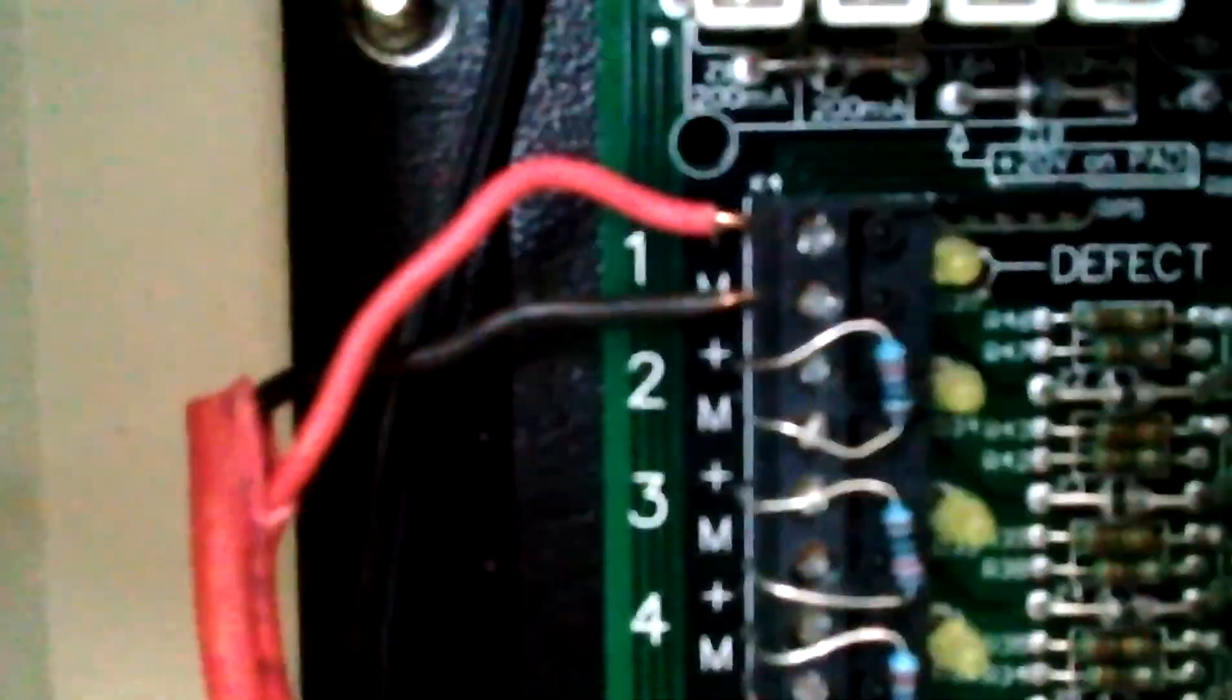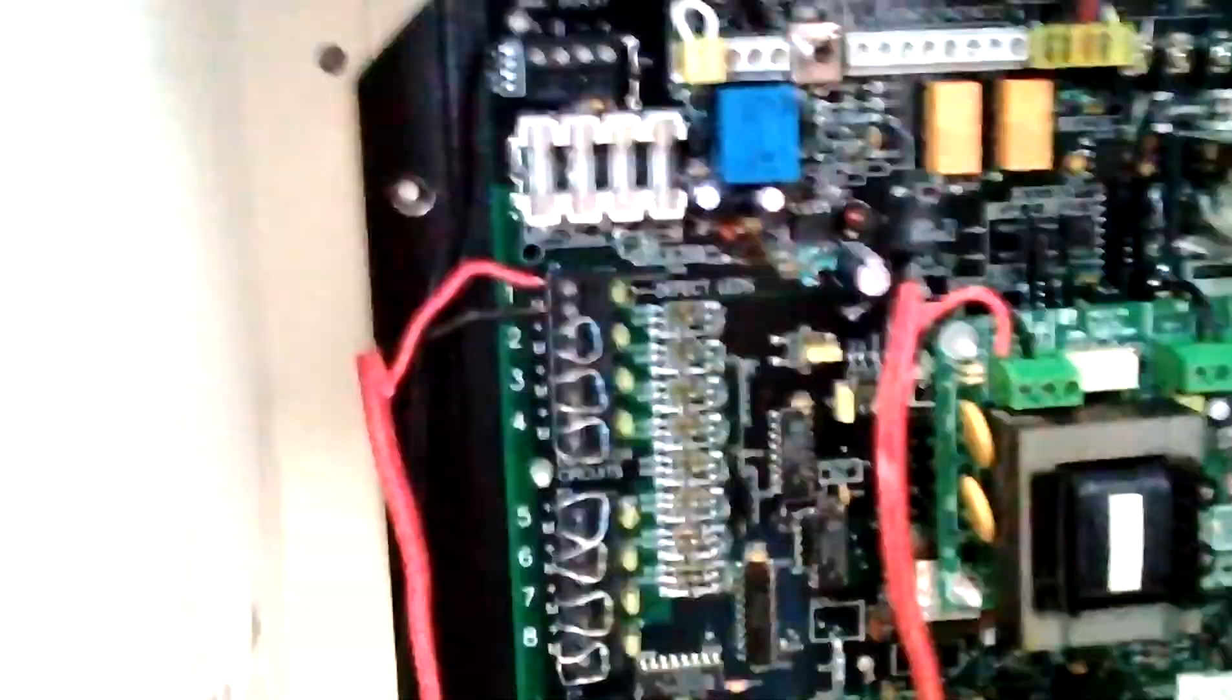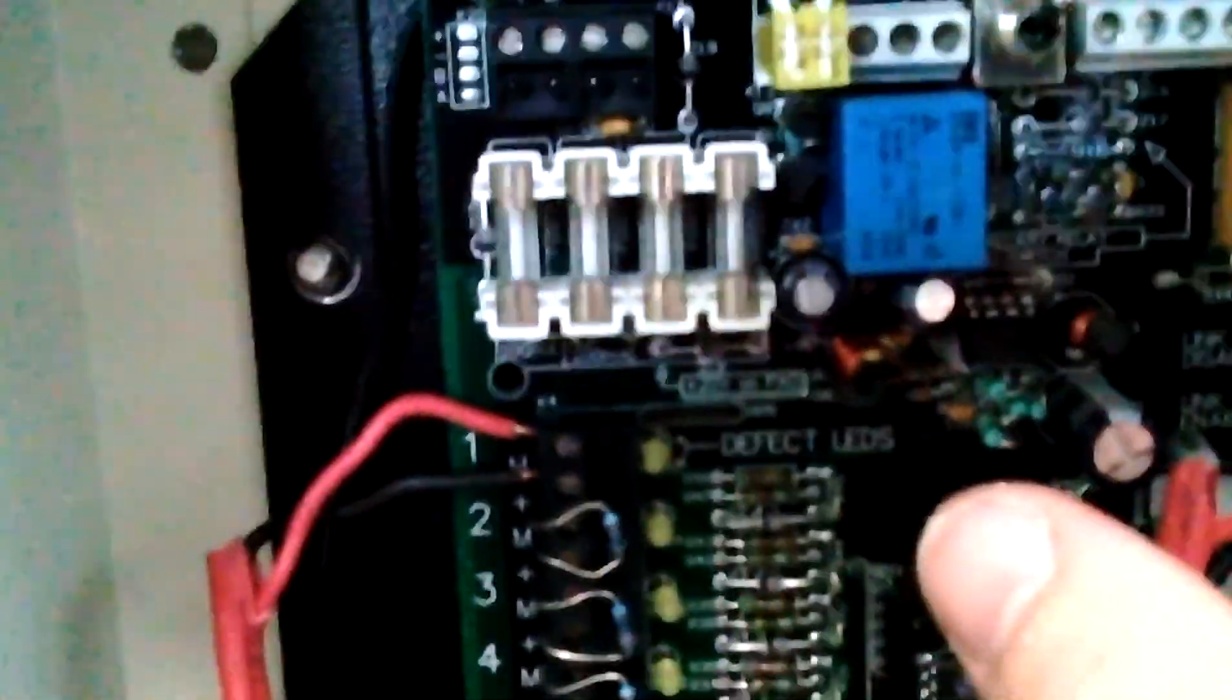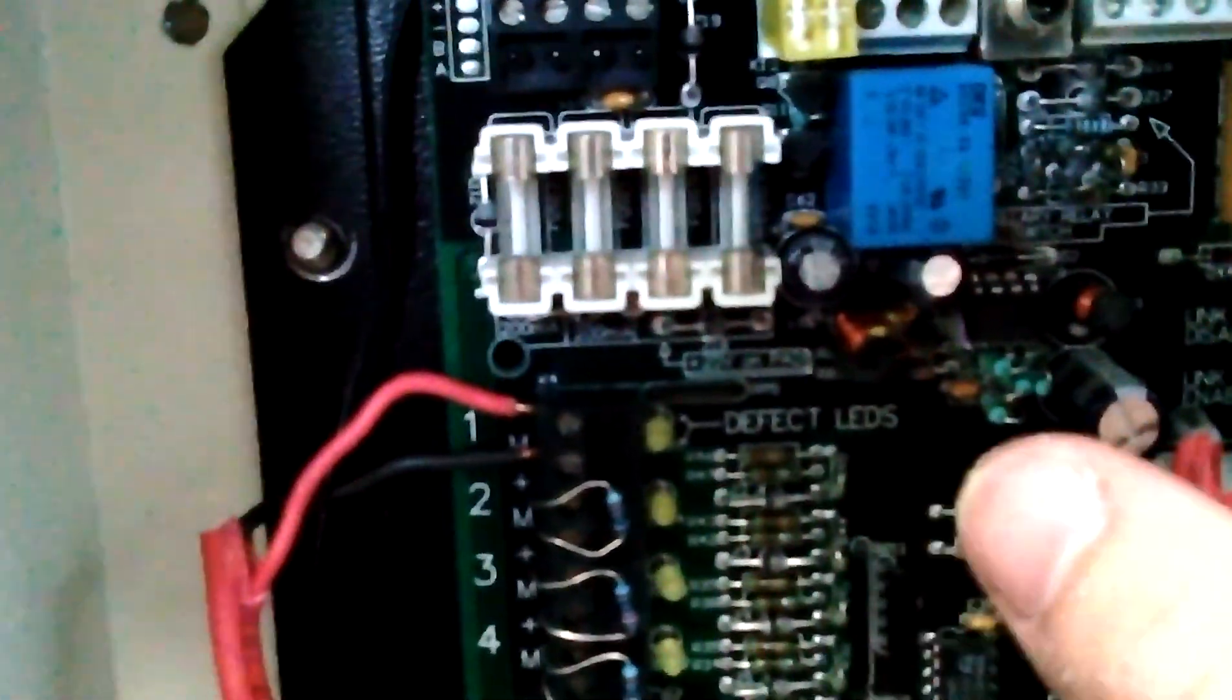So there's all the eight zones there. I've got every single one not in use except for zone one. The good thing about this panel, like my other one, is it's got an auxiliary relay. It's got a sprinkler input. It's got fire, defect relays, two separate bell outputs for high current, five amps, I think. So it's just all around a lot better, and you can put mimic displays in, which I will be getting. So that'll be cool.